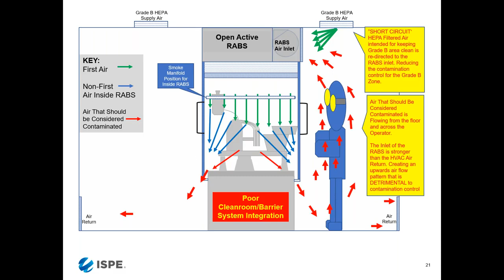What is happening? The air comes down, goes over the operator onto the inlet grill of the RABS. Isn't the operator sacred here? Because this is the operator who will be opening the door, and floors are dirty or clean - they're dirty. So you see this air is coming down, lifting the dirt over the operator into the inlet grid. What is he doing, what is this air doing? It's contaminating the operator. That is why we see so many 483s and some data integrity issues, because we don't understand this concept.